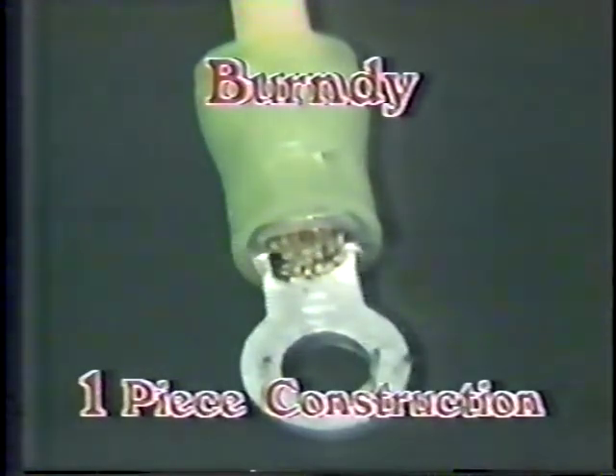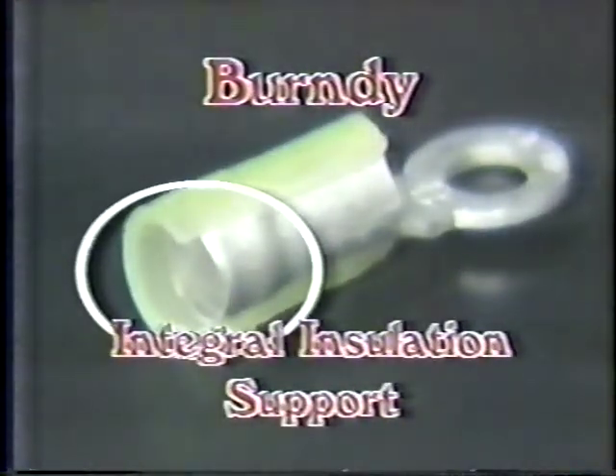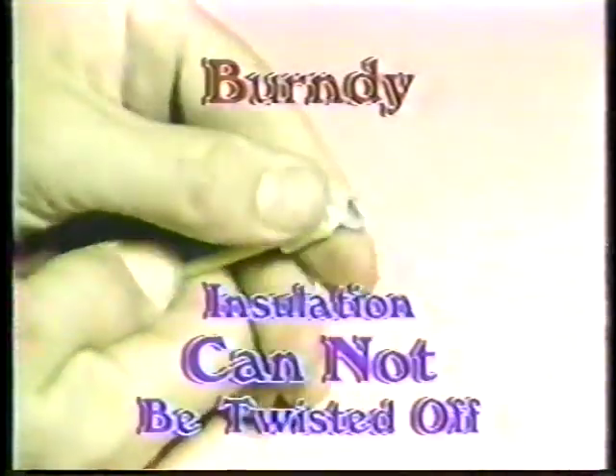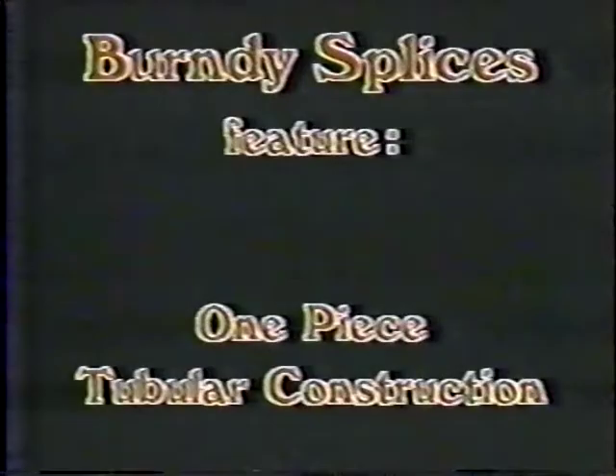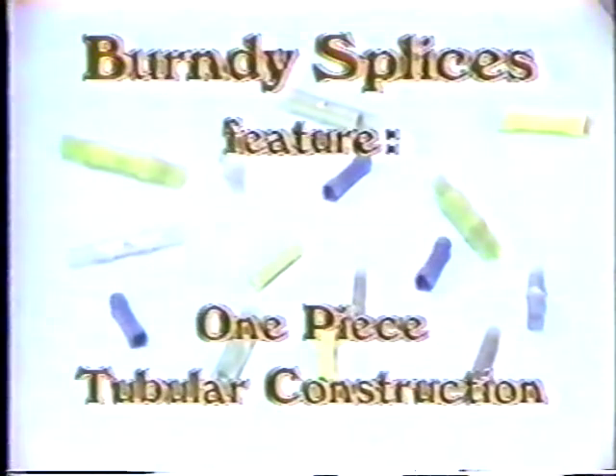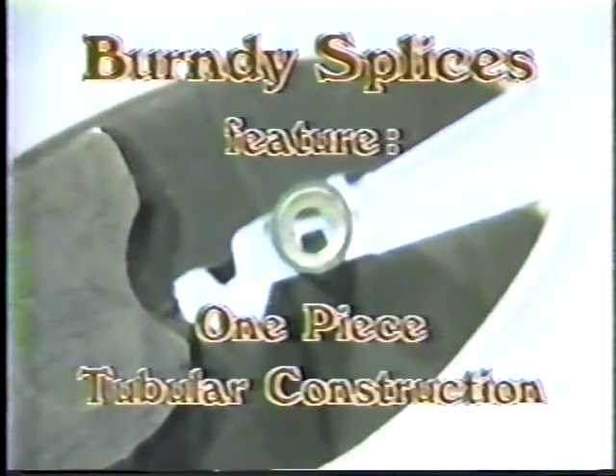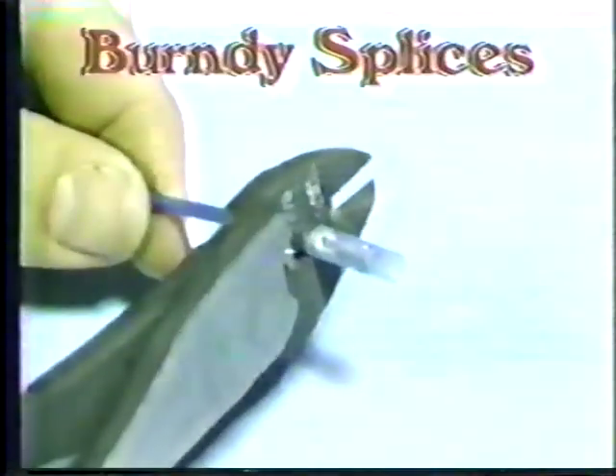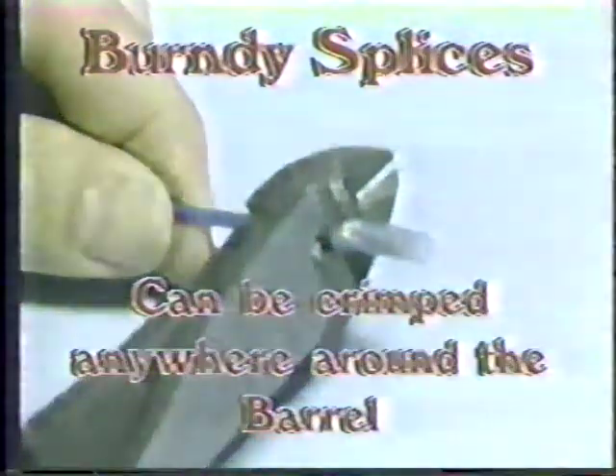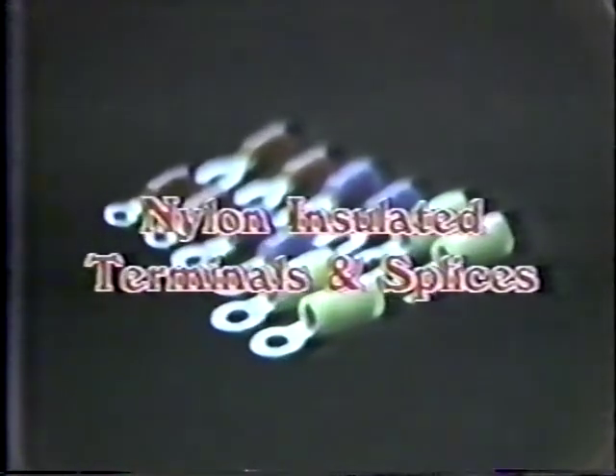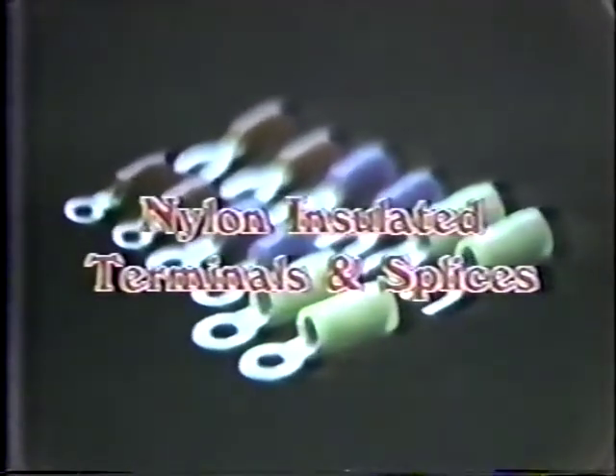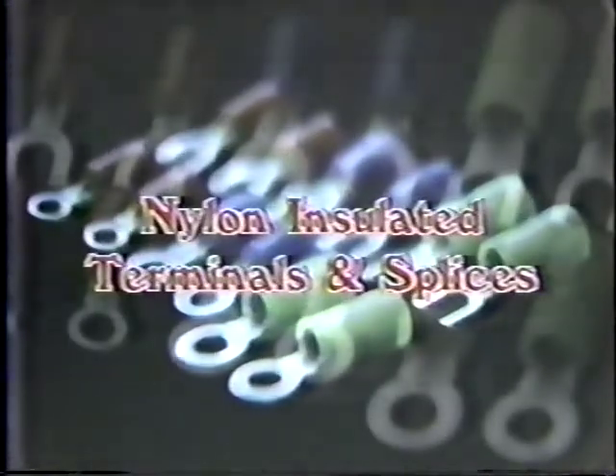Burndy's unique design also features an integral insulation support, and our manufacturing techniques ensure that our insulation cannot be twisted off. All Burndy splices feature a one-piece tubular construction, which eliminates the possibility of folding or splitting seams. Since there are no seams, Burndy splices can be crimped anywhere around the barrel. For side-by-side installation in industrial or oily applications, Burndy offers a full line of nylon-insulated terminals. Nylon is better suited to these environments because oil will attack vinyl insulations.